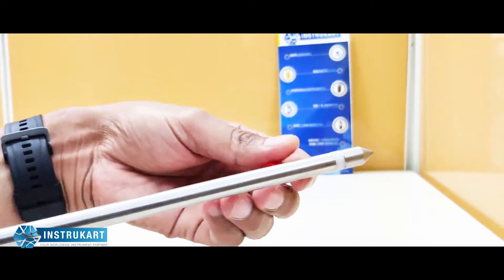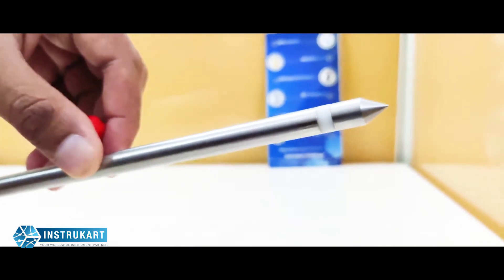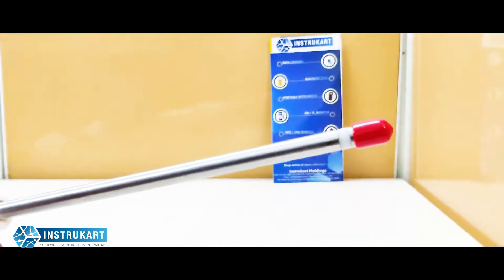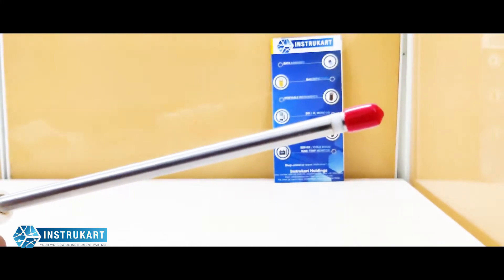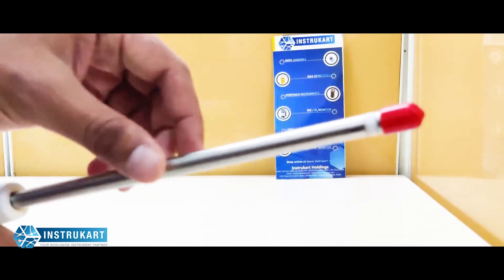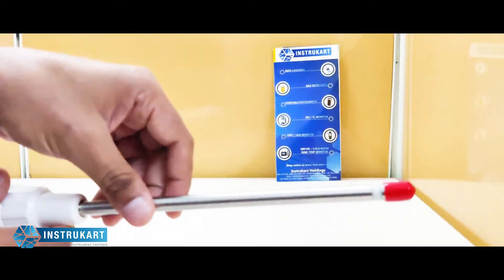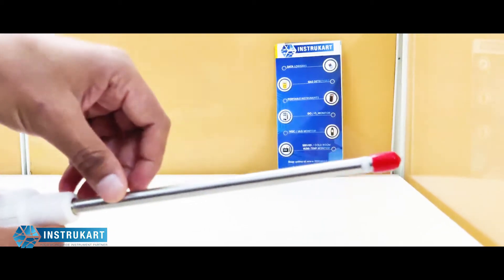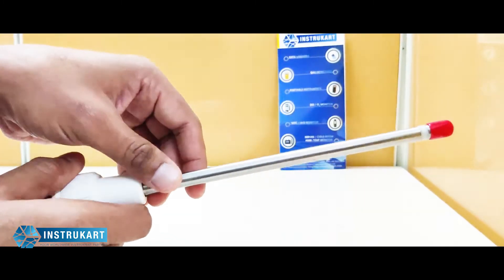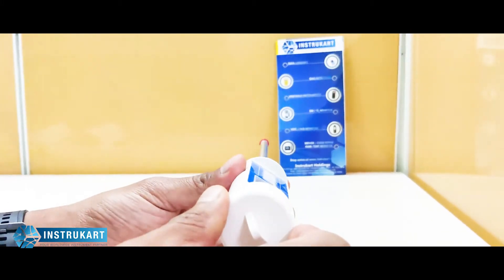If I show you the probe, the tip of this probe — it has got an accuracy of plus or minus 5 percent. It has got a two-pin moisture electrode and a sampling time of approximately 0.8 second.